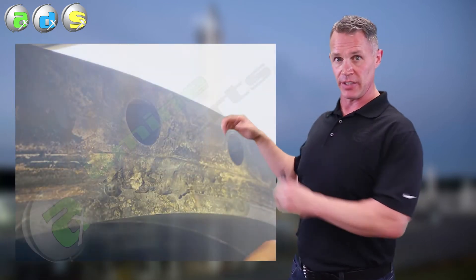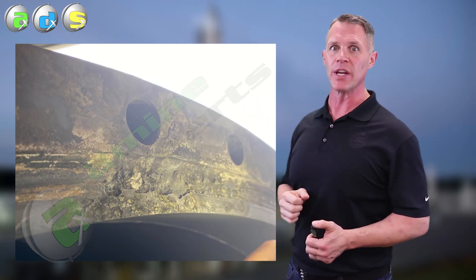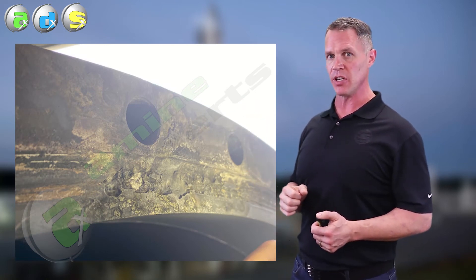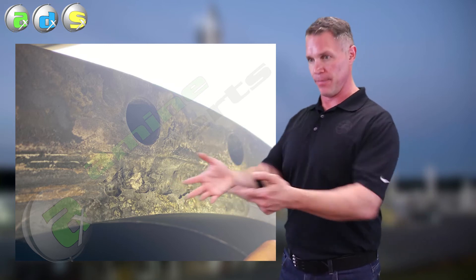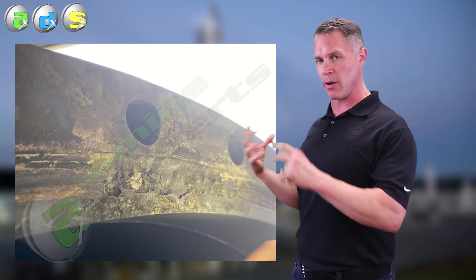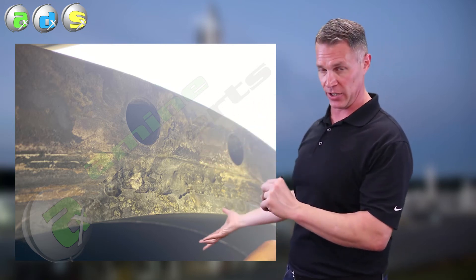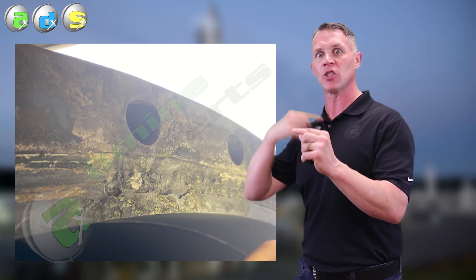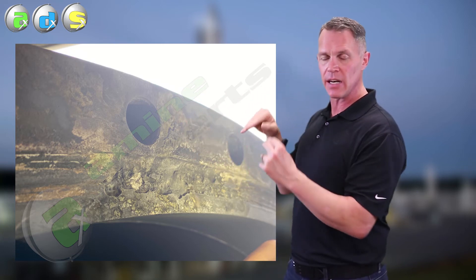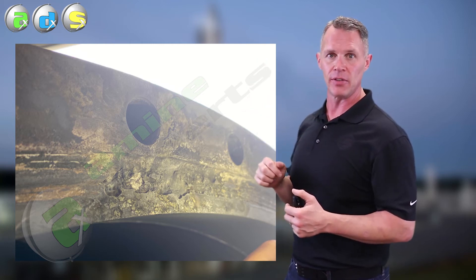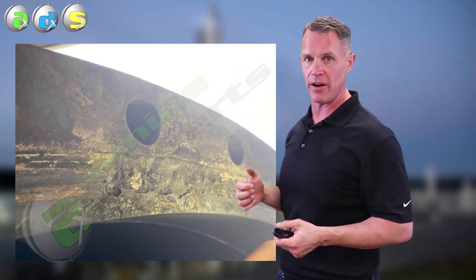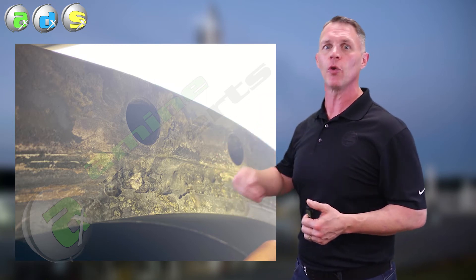Otherwise, you can wind up like these guys. Now, those graphs I just showed, this was the exact reason why this client of ours had hired us. It's because they were having a lot of reboiler corrosion and they wanted to know why. And that was why. But when we opened up the reboiler - this was a vertical thermal siphon reboiler - where the gaskets were, the gaskets were leaking. So there was actually a physical amine leakage. But around the gaskets was a lot of pitting because it's a stagnant area. Some gas got in between the gasket and the metal. No reason for the gas to leave that area. So it just sits there and hangs out and the CO2 just chewed away at the metal. Not what you want for your reboiler.